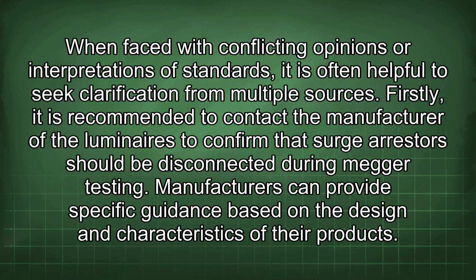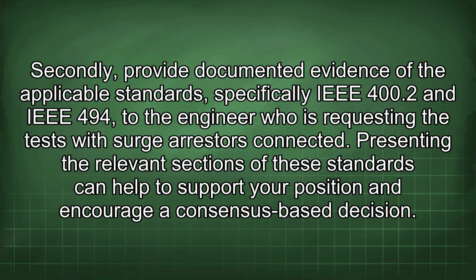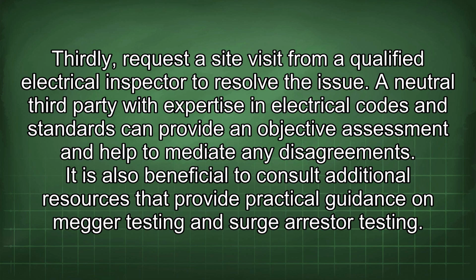When faced with conflicting opinions or interpretations of standards, it is often helpful to seek clarification from multiple sources. Firstly, it is recommended to contact the manufacturer of the luminaires to confirm that surge arrestors should be disconnected during Megger testing. Manufacturers can provide specific guidance based on the design and characteristics of their products. Secondly, provide documented evidence of the applicable standards, specifically IEEE 400.2 and IEEE 494, to the engineer who is requesting the tests with surge arrestors connected. Presenting the relevant sections of these standards can help to support your position and encourage a consensus-based decision. Thirdly, request a site visit from a qualified electrical inspector to resolve the issue.